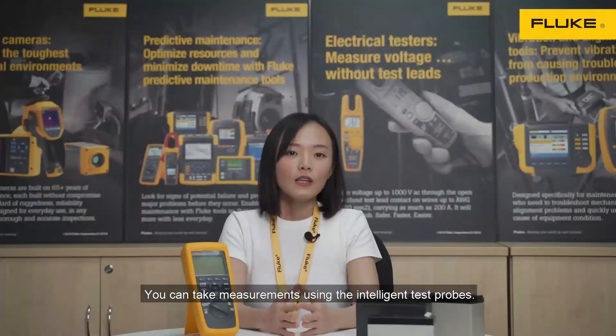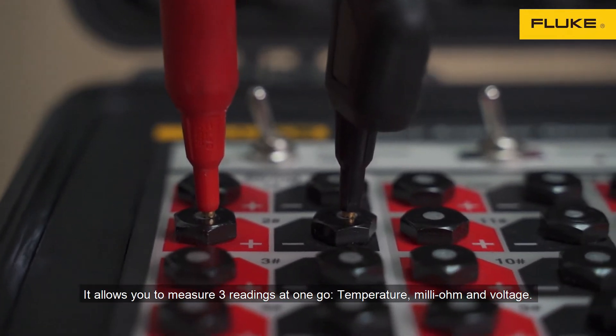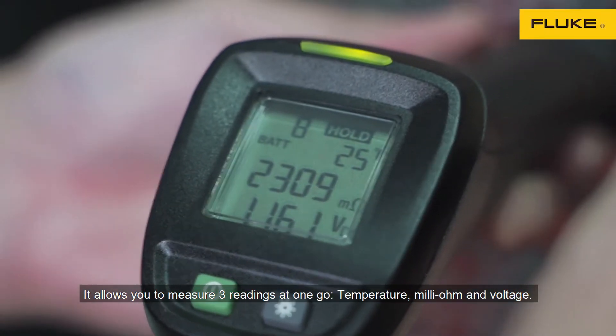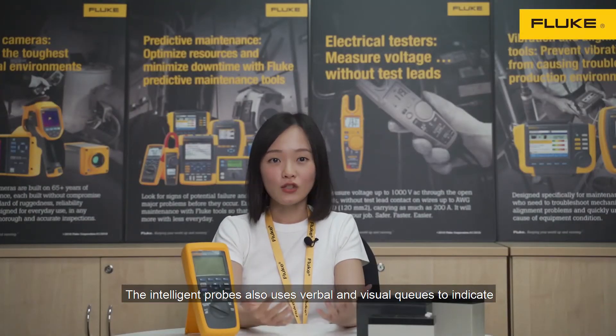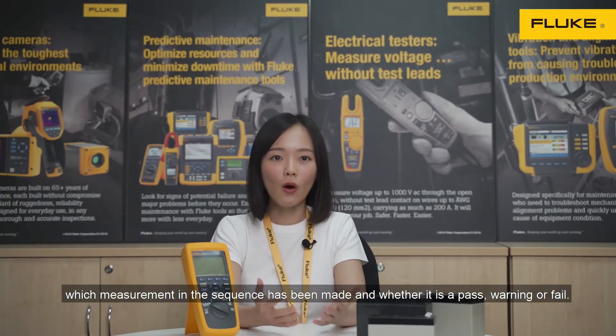So how do you do this? You can take measurements using the intelligent test probes. It allows you to measure three readings at one go: temperature, milli-ohm, and voltage. The intelligent probes also use verbal and visual cues to indicate which measurement in the sequence has been made and whether it is a pass, warning, or fail.